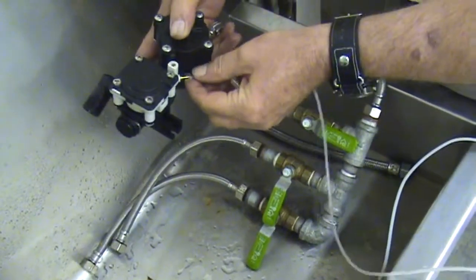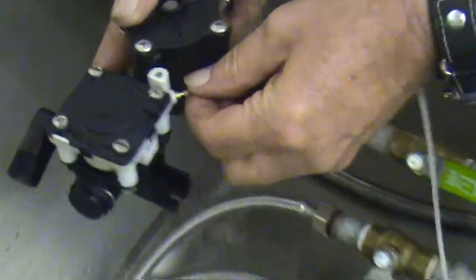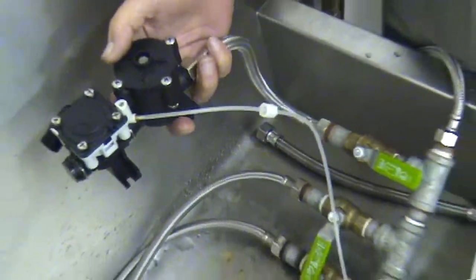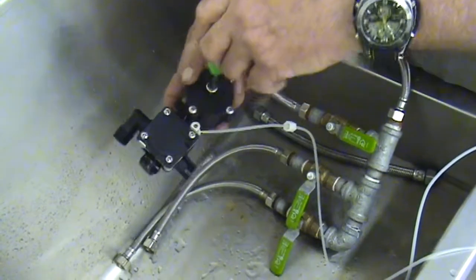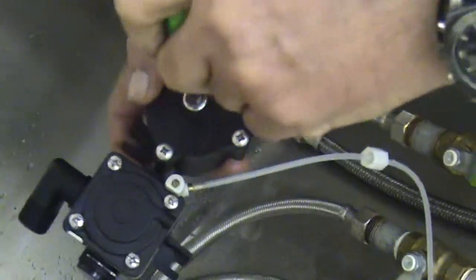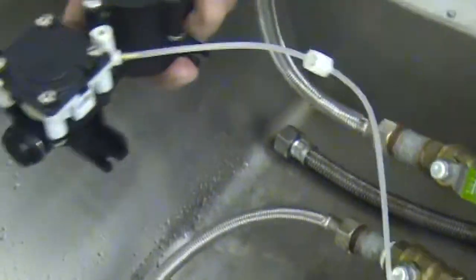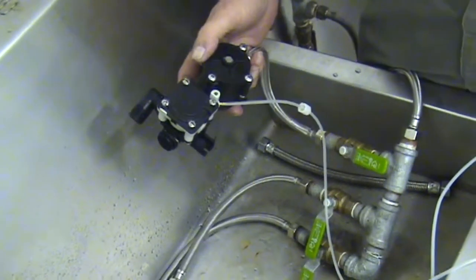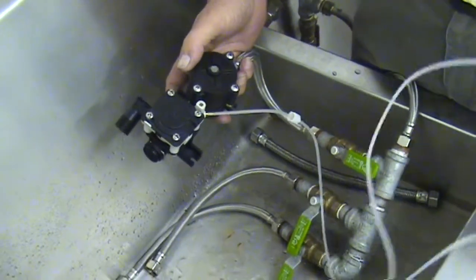We'll connect our spare push button again. Open our stop check. The valve came on and shut off. That's a good indication that our water diaphragm is working okay.